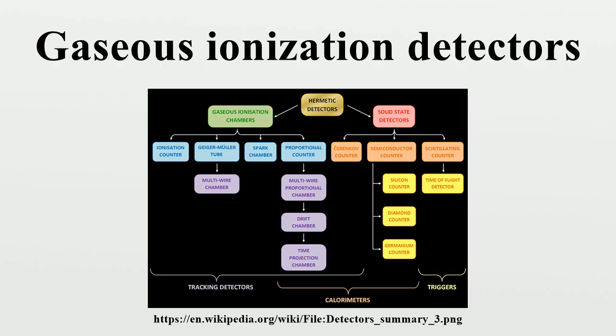Ion chambers are preferred for high radiation dose rates because they have no dead time, a phenomenon which affects the accuracy of the Geiger-Müller tube at high dose rates. The advantages are good uniform response to gamma radiation and accurate overall dose reading. They will measure very high radiation rates, and sustained high radiation levels do not degrade the fill gas. The disadvantages are very low electronic output requiring a sophisticated electrometer circuit, and operation and accuracy easily affected by moisture.